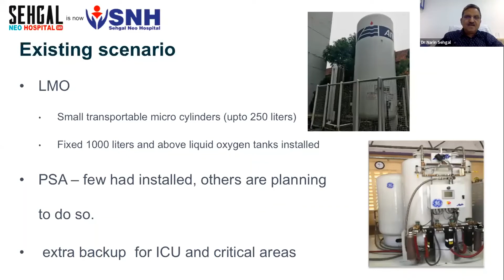There is another learning for us, which we have already acted on: extra backup for ICU is required. These things are usually present in big hospitals, but for smaller hospitals, I think it is a necessity. We need similar facilities, and we have to do it in our own way, at our own level. So finally, in short, if we talk of recommendations for small hospitals, we must have an oxygen outlet on each bed, which is missing from smaller hospitals. We must have a manifold with D-type cylinders and try to have a backup with automatic switchover. I think it is a must. We must aim for this. It's a small cost initially, but it saves you a lot of trouble.